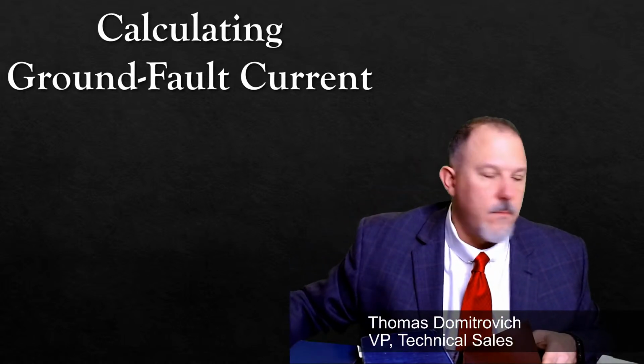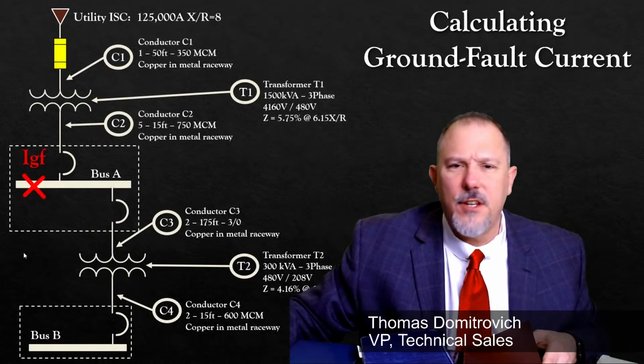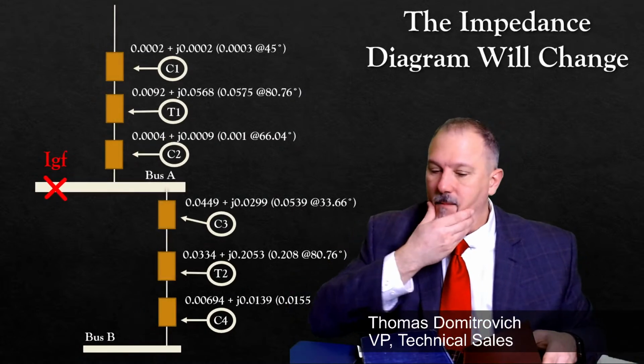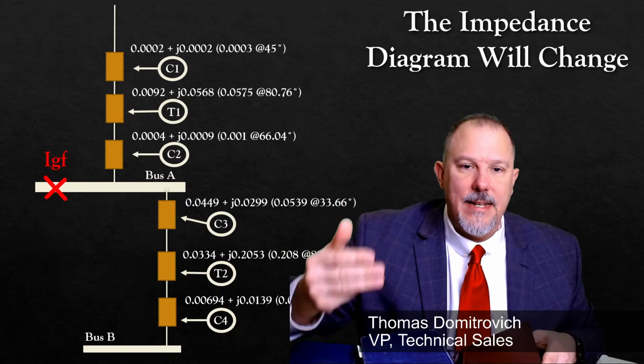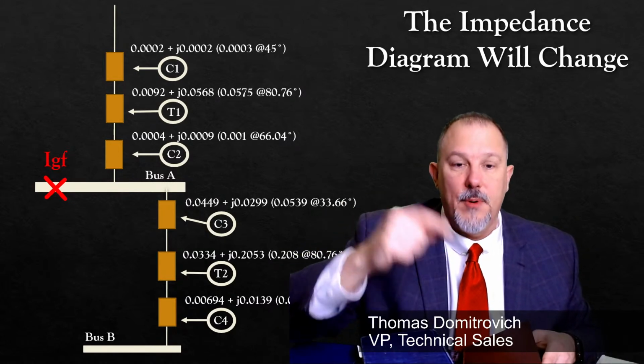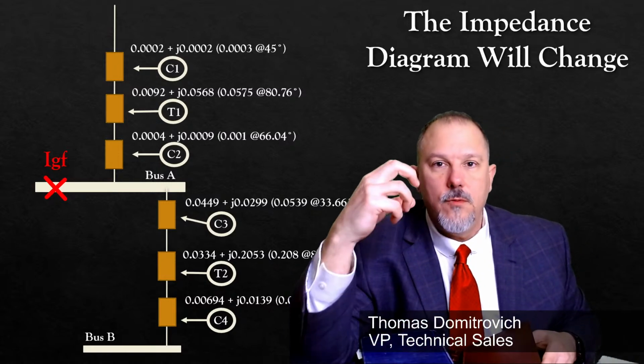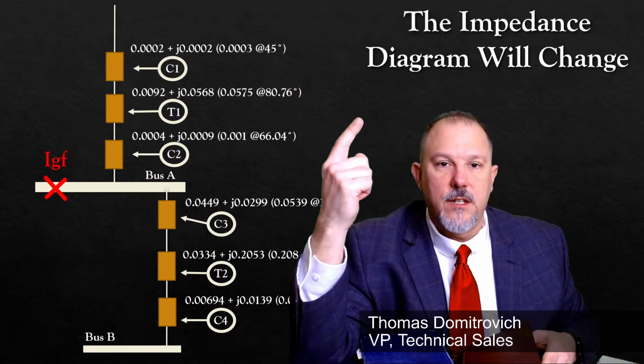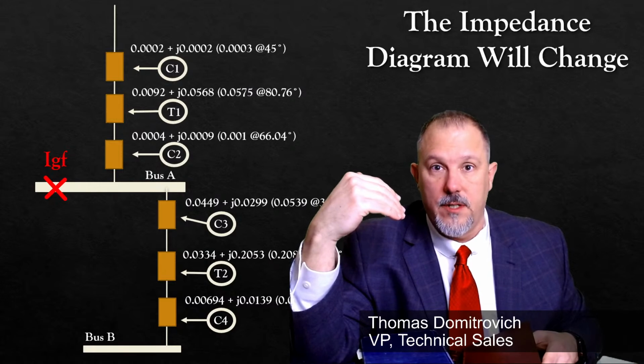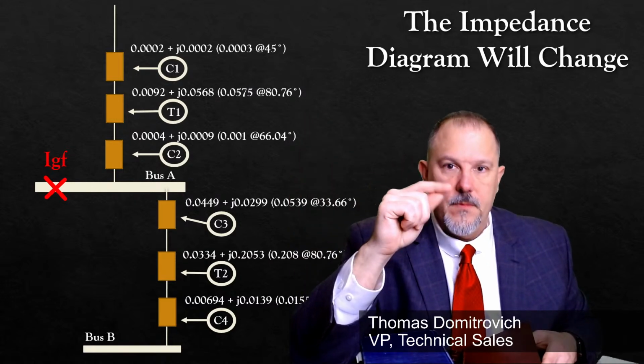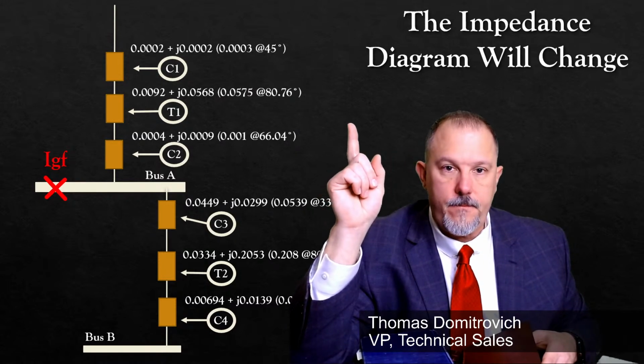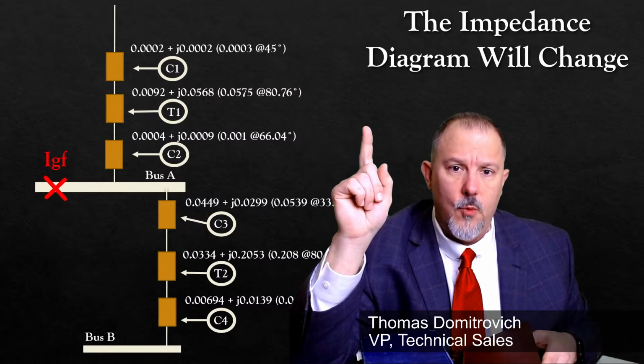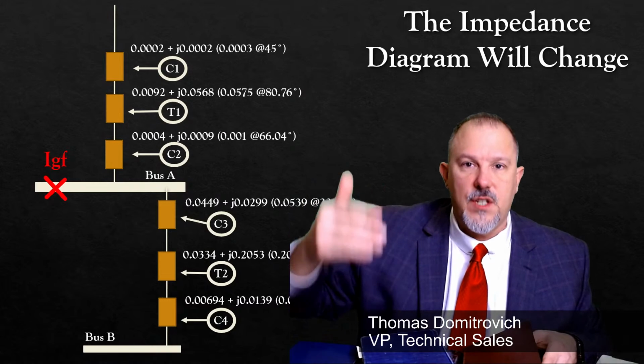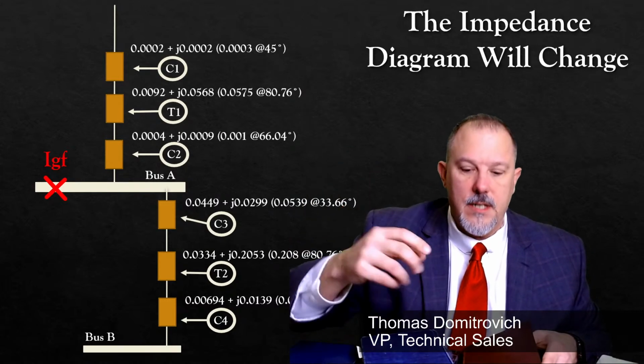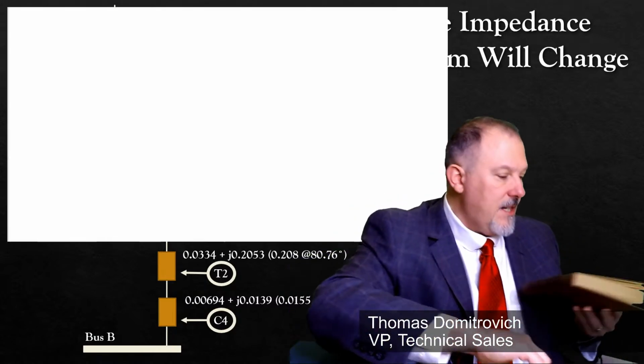This diagram, so you gotta follow me now. So remember this impedance diagram. These impedances, C1, T1, and C2, if I'm going to calculate the ground fault current at bus A, I don't just create the zero sequence impedances of C1, T1, and C2 and say, okay, I'm going to take those zero sequence and calculate ground fault current. What you're seeing here is the positive sequence impedances. When we calculate the three-phase bolted fault, that is based upon the positive sequence impedances.